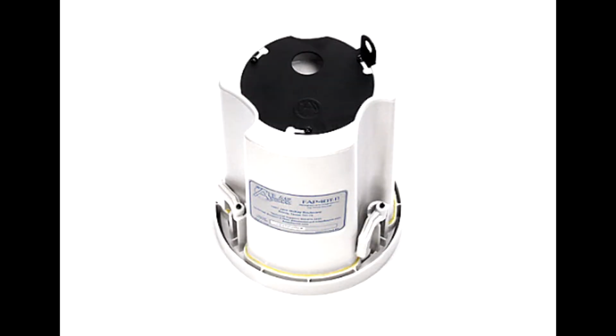To attach the wires to the speakers, remove the backplate. 2 screws are found under the speaker's backplate. The wires will connect to these 2 screws. The speaker is not polarized, and therefore it doesn't matter whether negative or positive is connected to either screw. Cut a hole in your tile ceiling with the template that came with the speaker. To install the speaker, make sure that you use the metal bracket that came with it for extra support.